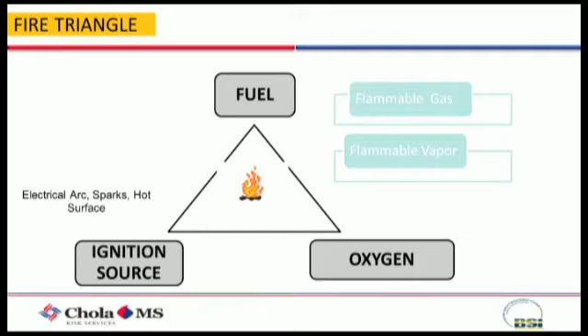To understand hazardous area classification, we need the concept of the fire triangle. The only controllable element is the ignition source. If we design our electrical or instrumentation equipment so that it cannot become a source of ignition, that is the concept behind hazardous area classification. We do this to select proper electrical equipment.